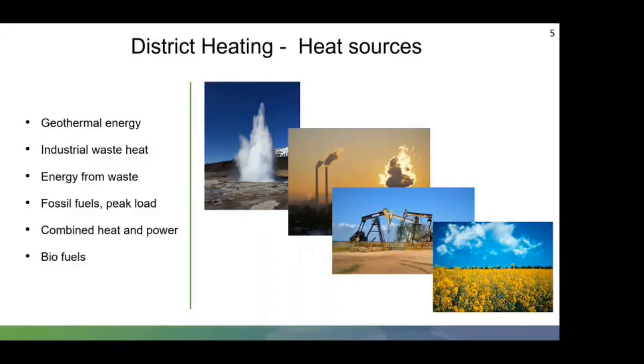The heat source offering is a constantly changing landscape as we look at more sustainable solutions for heat production. For example, river source heat pumps and hybrid systems made up of combined technologies, which can include solar thermal, heat pumps, CHP, heat recovery, especially heat recovery from things like data centres where a lot of heat is generated. Can that heat be utilised in a district heat network? Along with other emerging technologies to the market. One thing to always remember is that the principles in the heat network are the same. A heat source, or heat sources in a hybrid system, are used to provide heat along a pipework, which is then commonly transferred via plate heat exchangers to the liquid circulating around the district heat network.